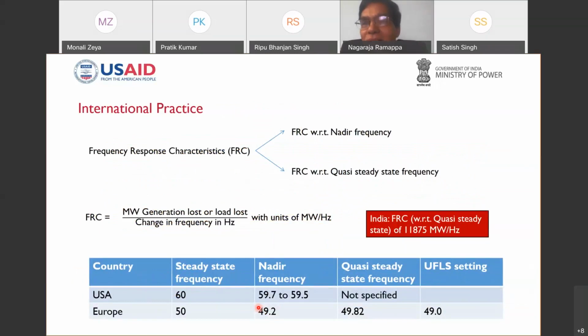Here we need to understand, just to have a mathematical modeling, a bit about how the frequency response characteristic is defined. In the Indian context, it is defined as megawatt generation lost or load lost divided by the change in frequency in Hertz, megawatt per Hertz. In some of the European countries, they talk about megawatt divided by 0.1 Hertz.